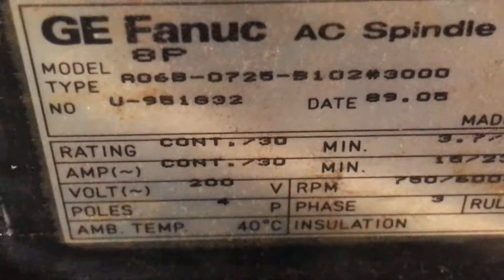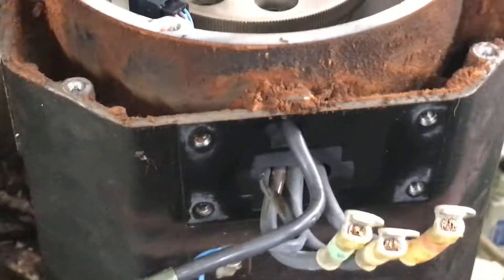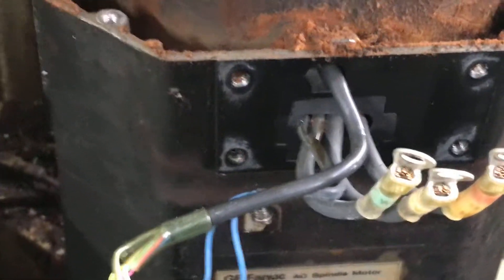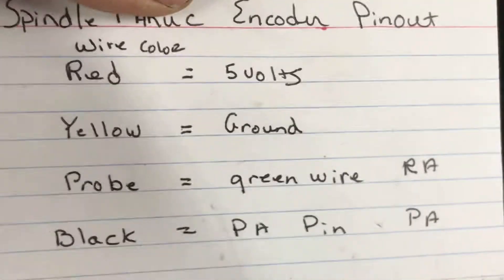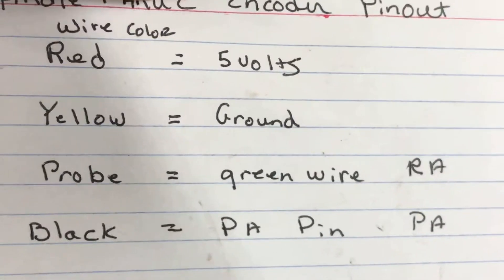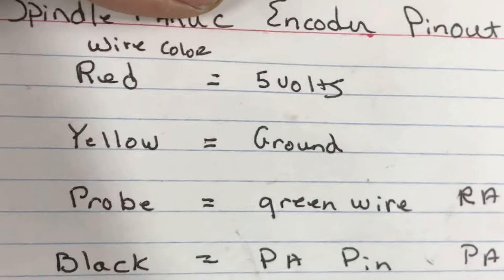It's an A06B-0725. I'm going to come out here next with a meter to measure the inductance. Before I put everything back together I'm going to vacuum it all out, clean it up, and put the top back on. I've checked the encoder pulse on PA and PB and I am good.